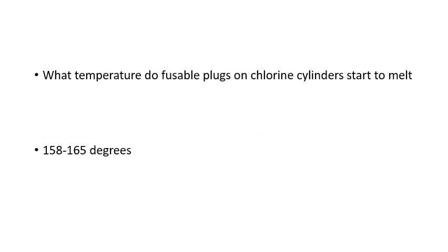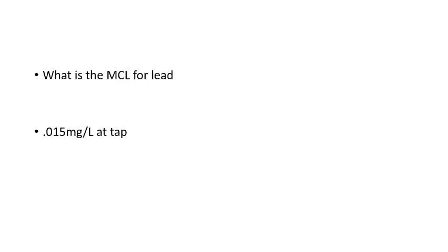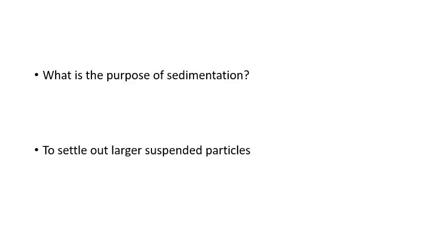At what temperature do fusible plugs on chlorine cylinders start to melt? 158 to 165 degrees Fahrenheit. What is the MCL for lead? 0.015 milligrams per liter at tap. What is the purpose of sedimentation? To settle out larger suspended particles.